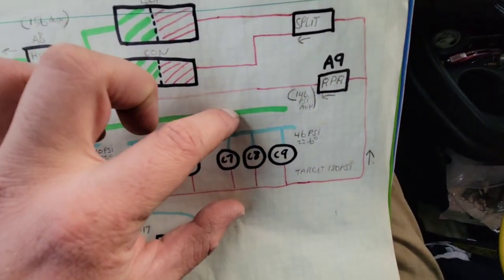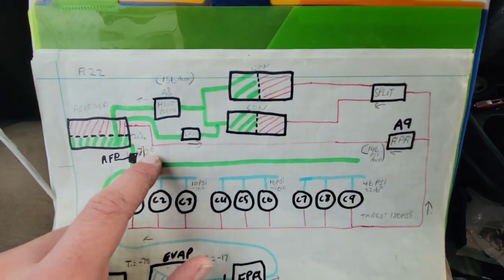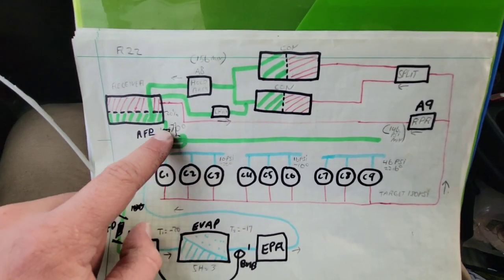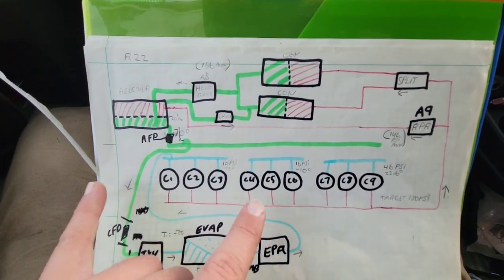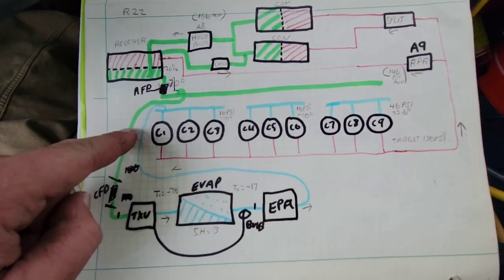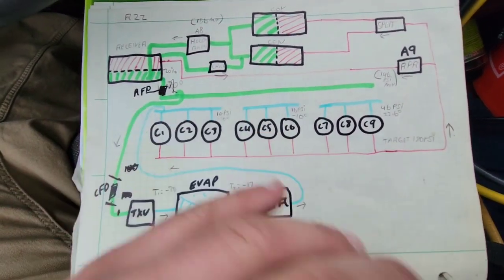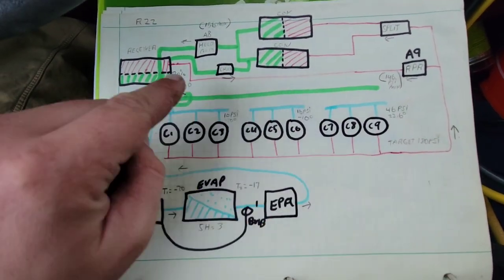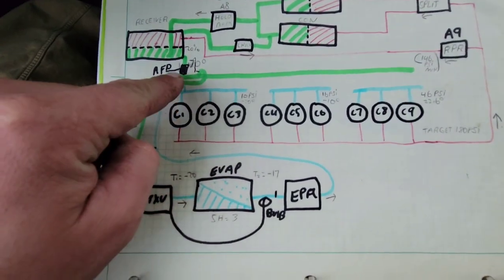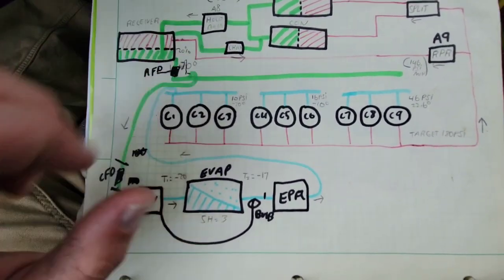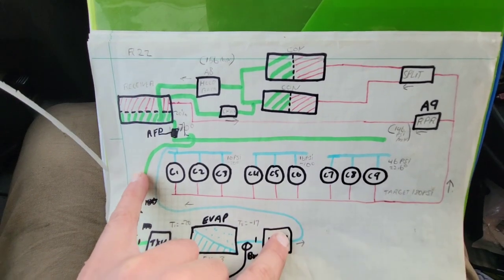So now we know our pressures are right, our flow is right, at least to here. And now, what do we look at? Before we go to the EPR, the suction line solenoid, and those types of activation devices, check your ball valves for your circuit. You're going to have these two ball valves at the rack. Make sure they're open. Then our EPRs and our solenoid valves.